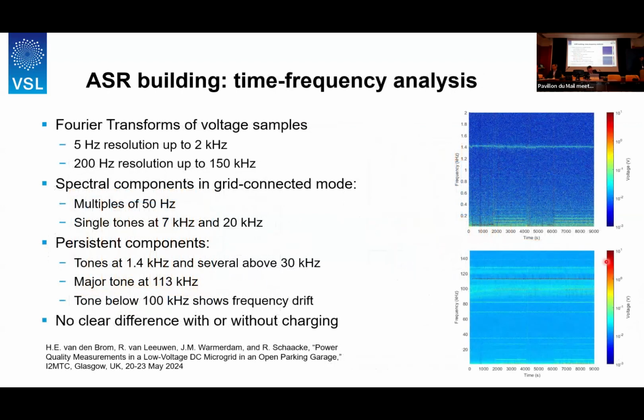Nevertheless, we did see something when we did the time frequency analysis. You can clearly see here, this is, by the way, from 0 to 2 kilohertz, and this is from 0 to 150 kilohertz with different resolution. And this is the time axis in both cases. And here you can see that when it's grid connected, there are 50 hertz components. Also when it's grid connected, you see in this graph that there are tones at 7 kilohertz and 20 kilohertz or so, which were not there when it was not in grid connected mode.